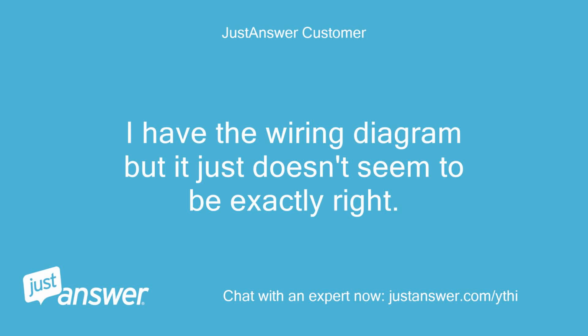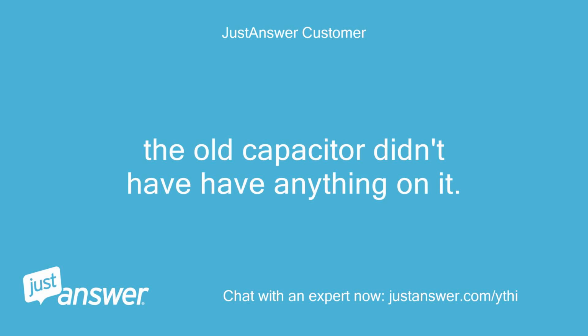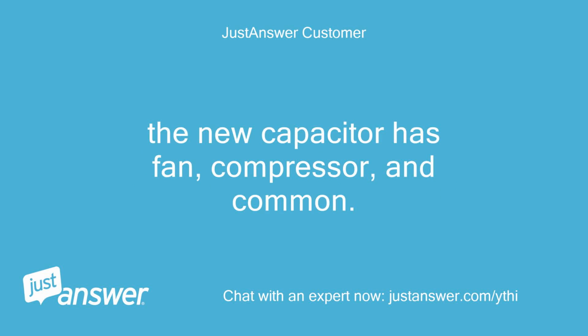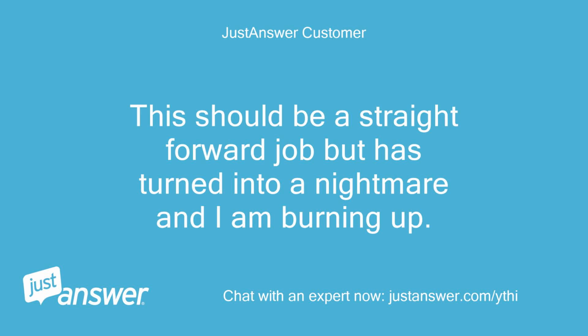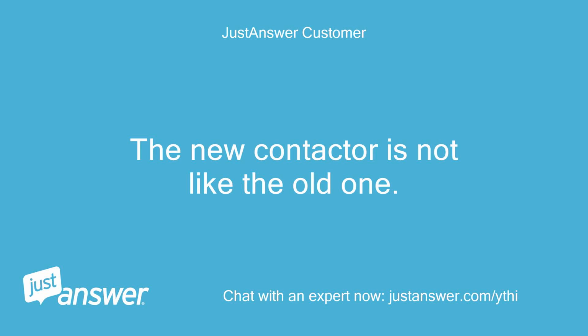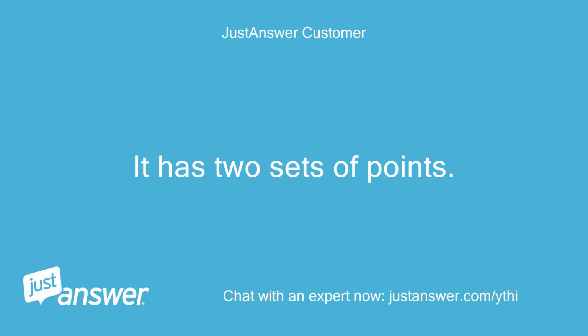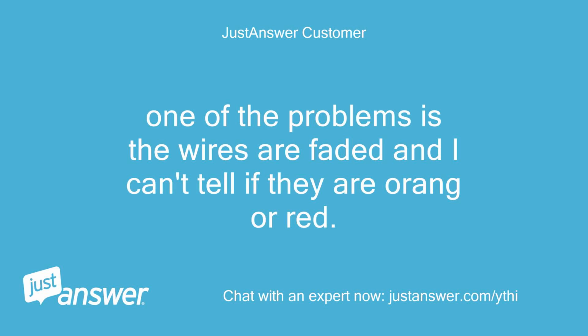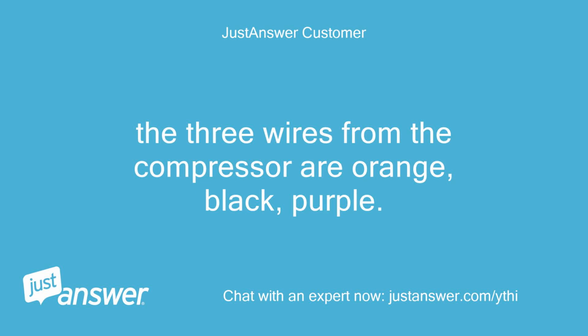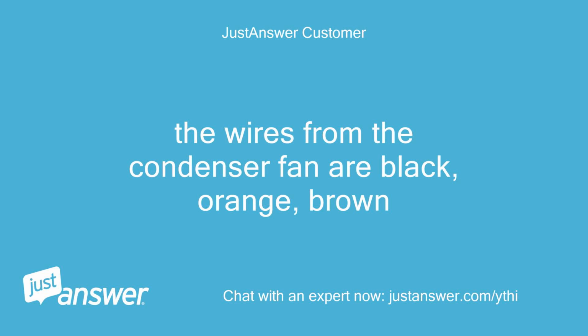I have the wiring diagram, but it just doesn't seem to be exactly right. The old capacitor didn't have anything on it. The new capacitor has fan, compressor, and common. This should be a straightforward job but has turned into a nightmare and I am burning up. The new contactor is not like the old one. It has 2 sets of points. One of the problems is the wires are faded and I can't tell if they are orange or red. The 3 wires from the compressor are orange, black, purple. The wires from the condenser fan are black, orange, brown.